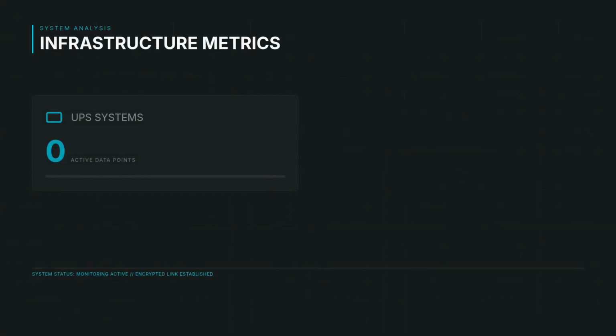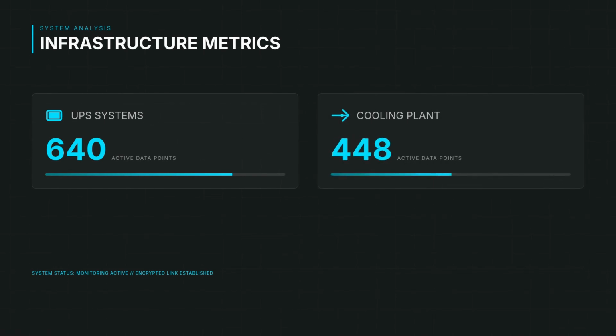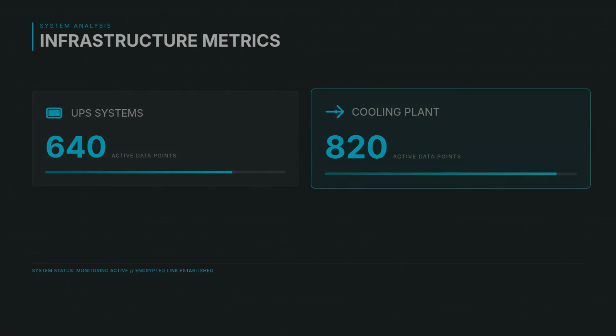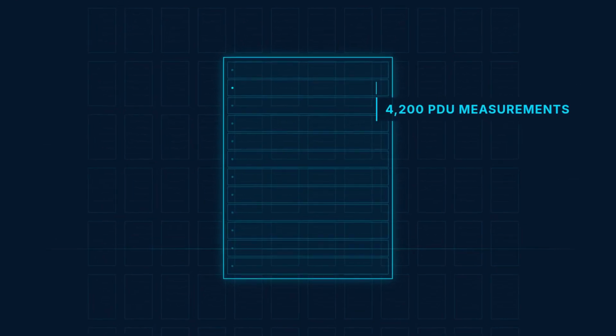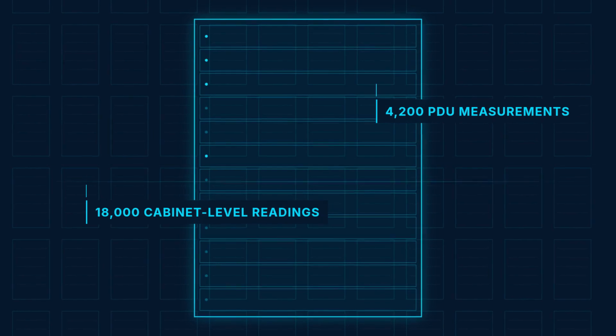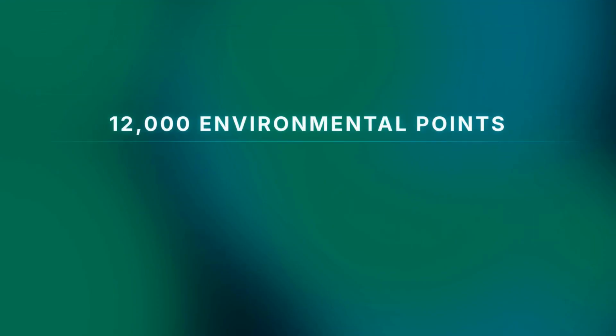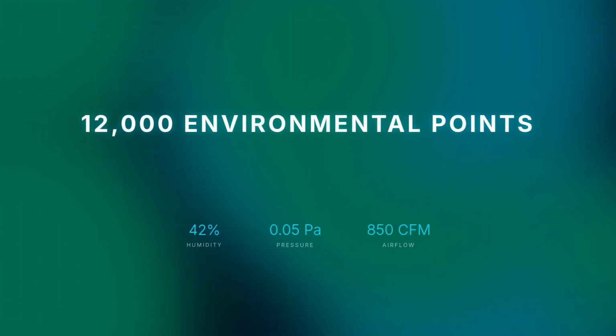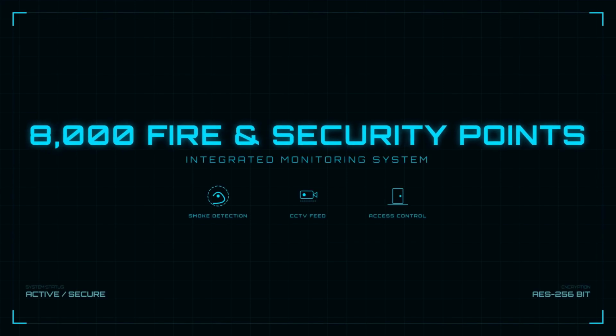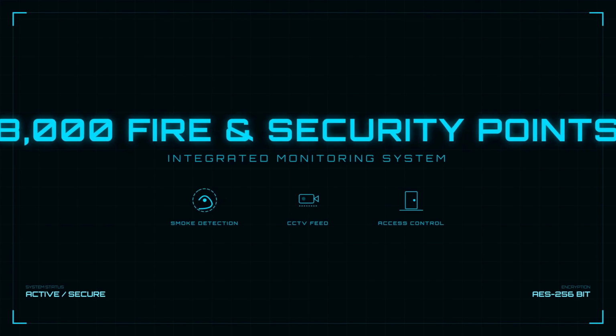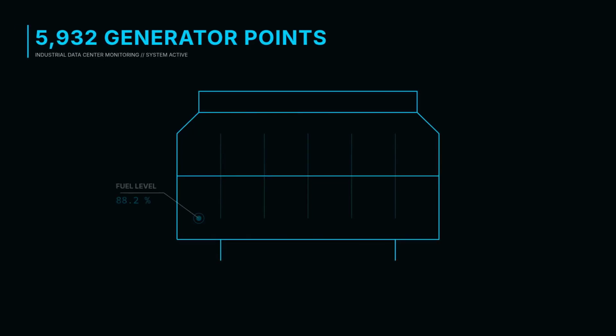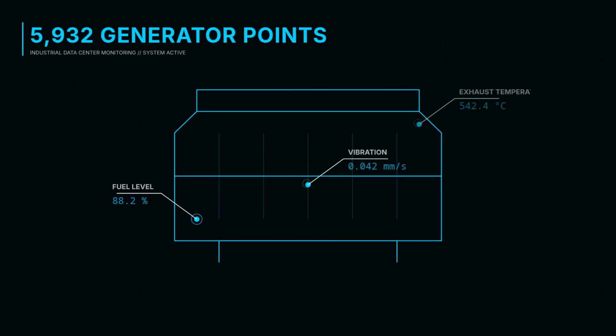We track per UPS output and autonomy, along with 800 cooling plant metrics, including pump pressures and chiller COP. The scale is immense, 4,200 PDU measurements and 18,000 cabinet-level power readings. Environmental monitoring adds another 12,000 points, tracking aisle temperatures, humidity, and underfloor pressure. Even fire and security are integrated, with 8,000 points covering smoke detection and access events. Finally, we monitor nearly 6,000 points across our generators and fuel farm, tracking vibration and exhaust temperatures. This entire 50,000-point hierarchy is measured in real time, with updates every 15 seconds.